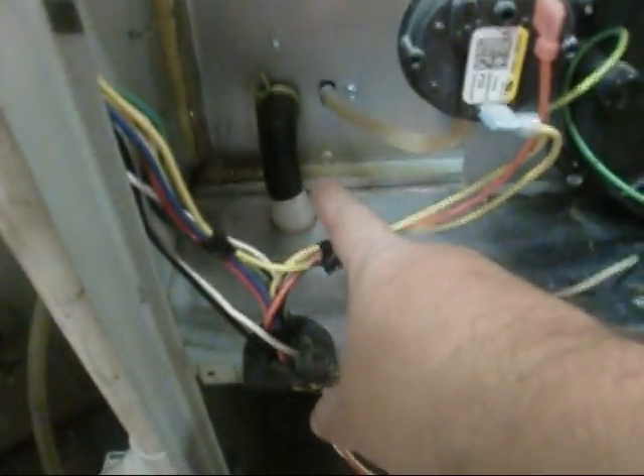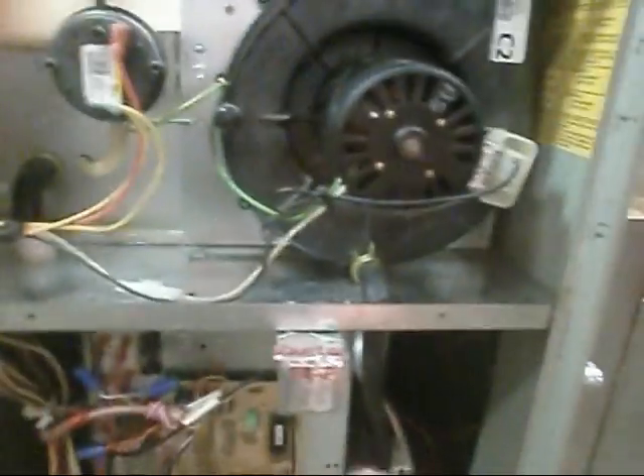She's probably going to sit in there for like 45 seconds to a minute before the fan fires up. I believe it's 45 seconds, but I want to cycle it a couple good times. It's kind of a pain in the butt with this secondary heat exchanger line, it runs in behind where the board is and it's trying to kink like heck. But I want to stick with it and make sure we're getting condensation.